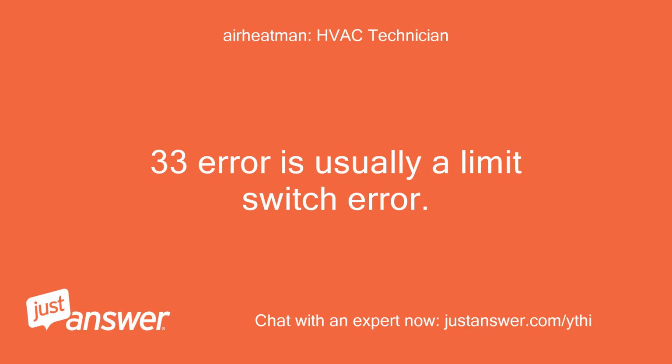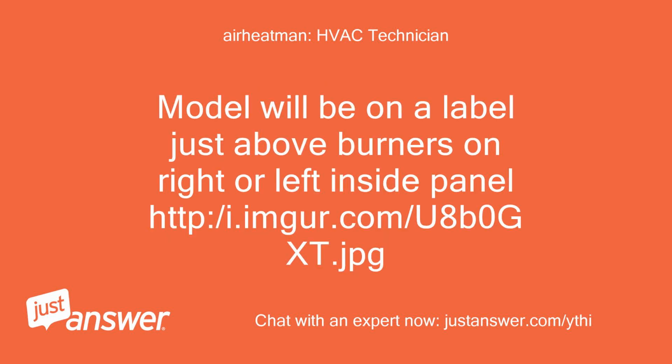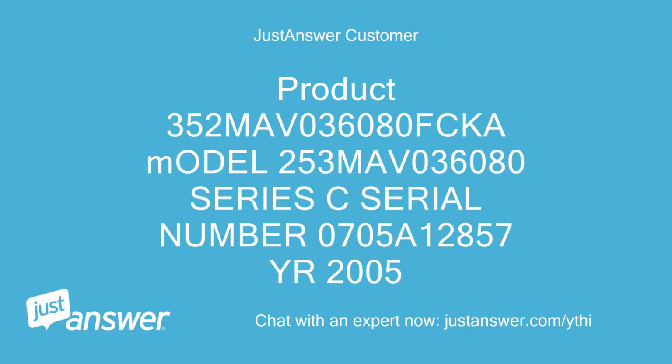33 error is usually a limit switch error. Can you give me complete model from inside furnace and burner compartment so I can provide guidance with this specific unit? Model will be on a label just above burners on right or left inside panel. Product 352 MAV 036080 FCKA Model 253 MAV 036080 Series C Serial Number 0705A12857 Year 2005.